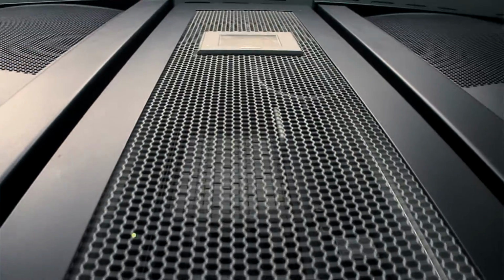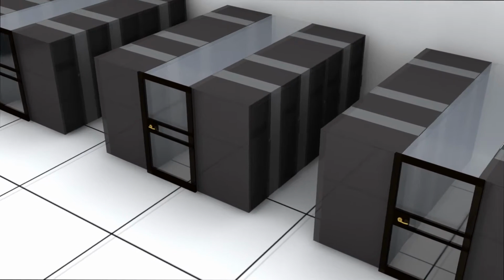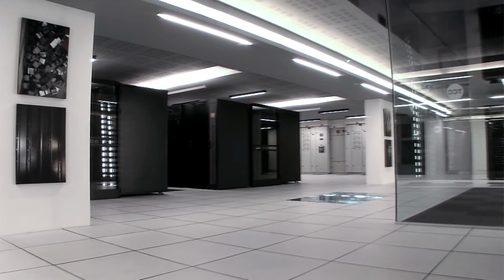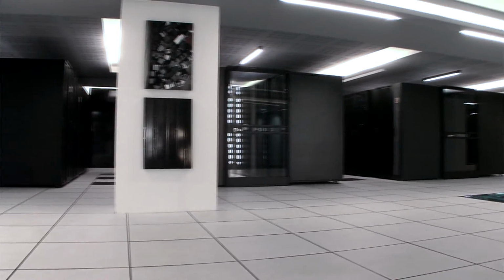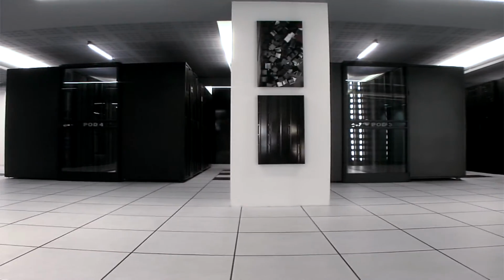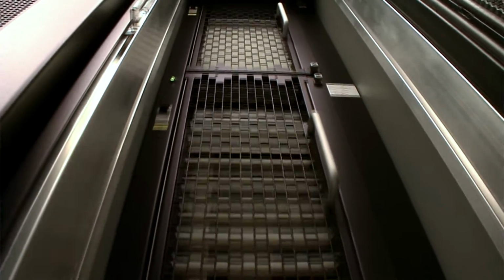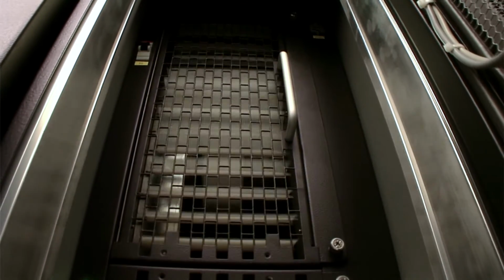Cooling of the servers is implemented using the in-row cooling technology. In this configuration, a warm corridor is created between 2 rows of server racks, which enclose the air by shutting the corridors. The trapped warm air is cooled by units located near the racks and is returned to the room space. This cooling technology is considered green, and it's about 30% more efficient than the traditional legacy technologies.